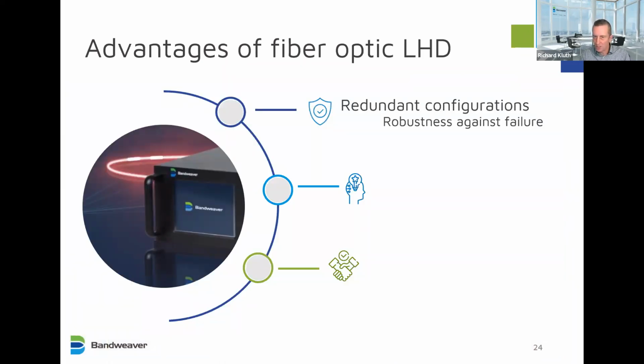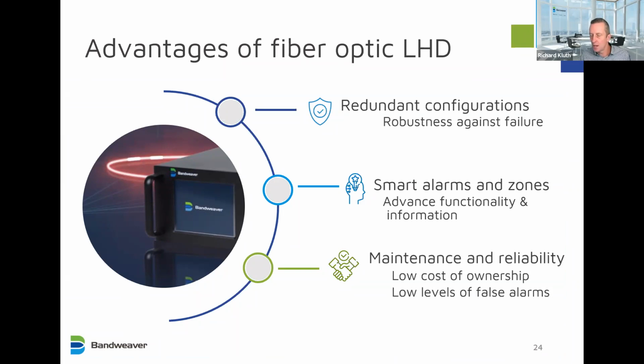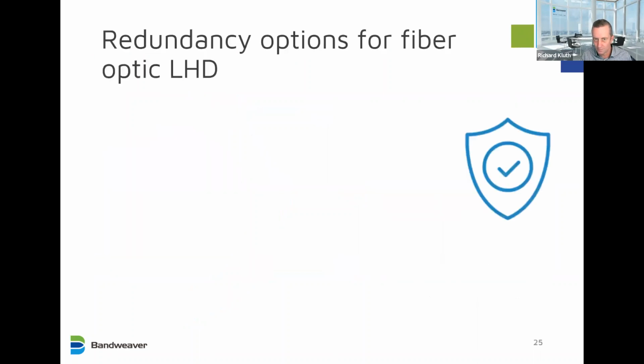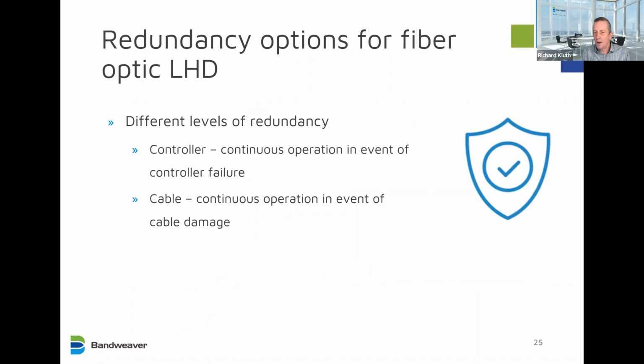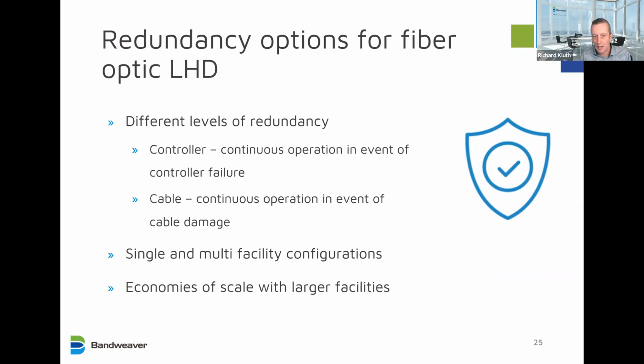The advantages we'll talk about in more detail now: redundant configurations, robustness against failure. We'll talk about the smart alarms and smart zones, the advanced functionality you get, and the low levels of maintenance and high reliability, leading to low cost of ownership and low levels of false alarms. So with fiber optic linear heat detection, you have different levels of redundancy. You have controller redundancy, which you typically get in other technologies: if you increase the number of units, you get redundancy. But we also have cable redundancy, so you have continuous operation in the event of cable damage. This scales up: with a single facility you typically need twice the number of units, but with the multi-channel capability, as you scale up to larger facilities, you get economies of scale.